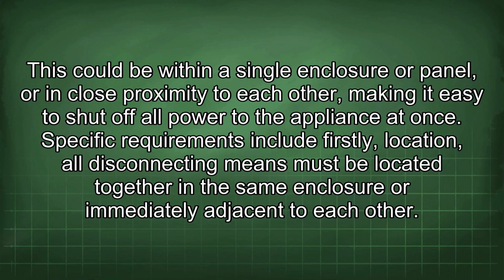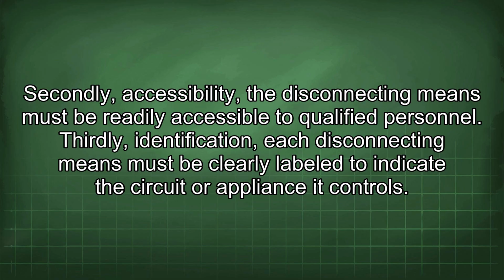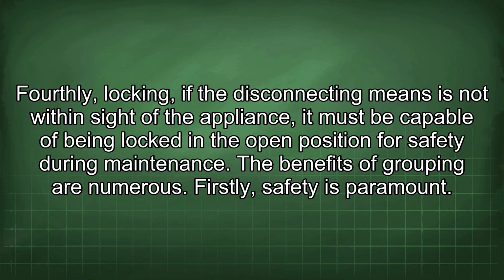All disconnecting means must be located together in the same enclosure or immediately adjacent to each other. Secondly, accessibility. The disconnecting means must be readily accessible to qualified personnel. Thirdly, identification. Each disconnecting means must be clearly labeled to indicate the circuit or appliance it controls. Fourthly, locking. If the disconnecting means is not within sight of the appliance, it must be capable of being locked in the open position for safety during maintenance.